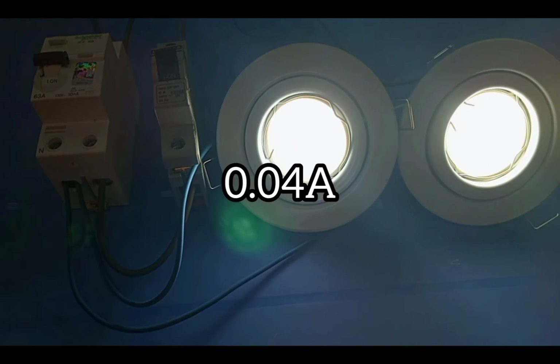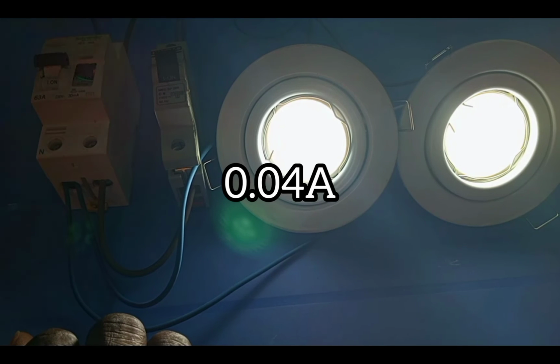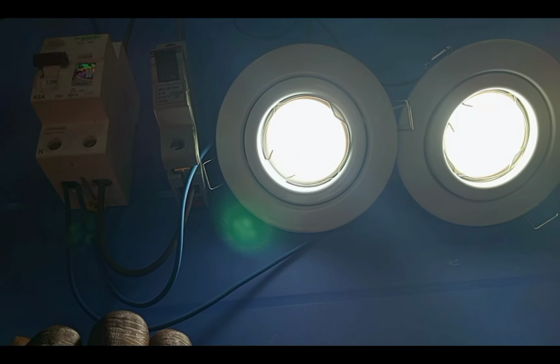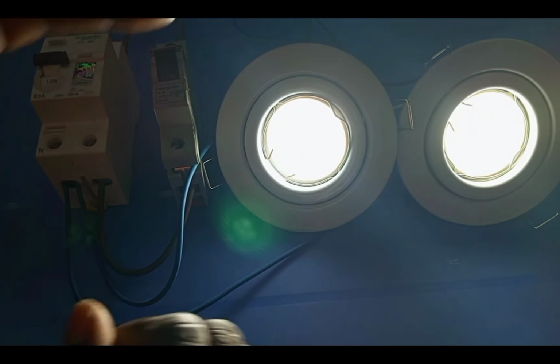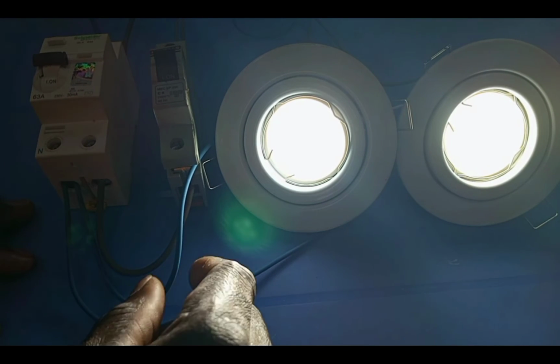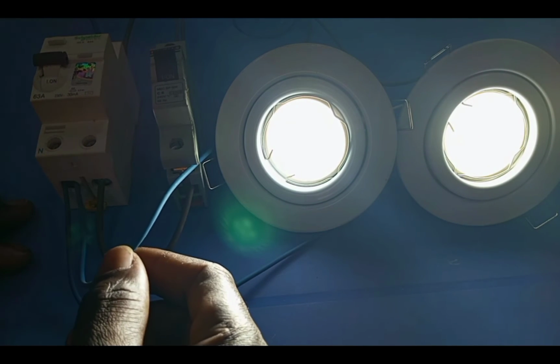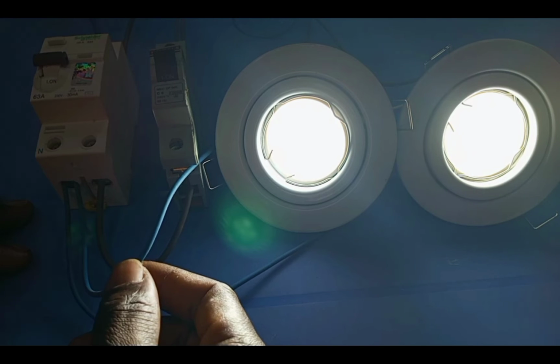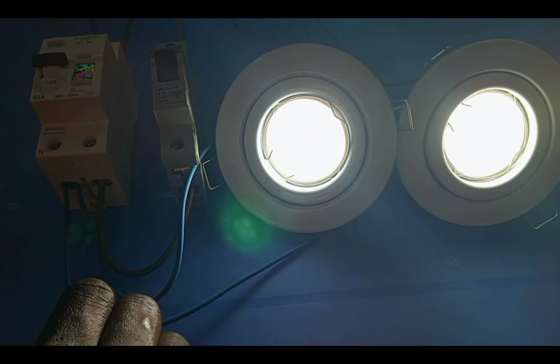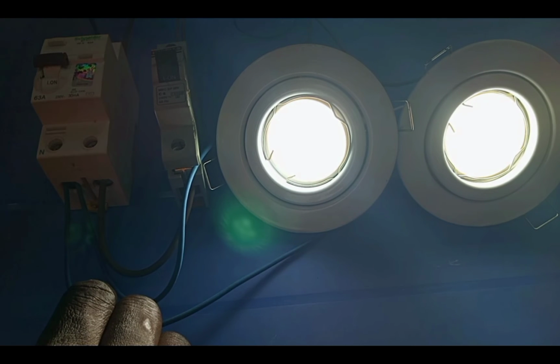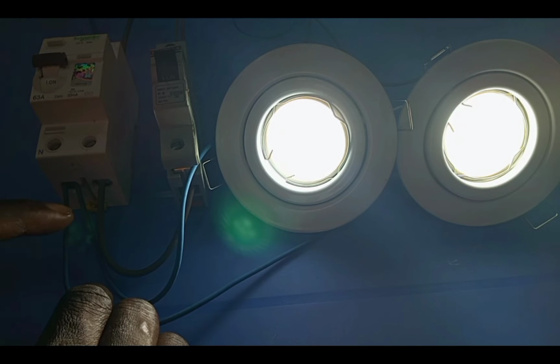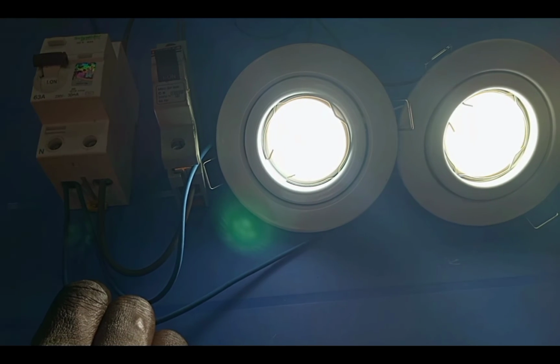All right, so in this case, 0.04 amps flows through the live wire to the lamps, but when it's coming back, it's only 0.02 amp that will be flowing. And so there will be an imbalance of 0.02 amps. It means you have 0.04 amps through the live wires, but you have only 0.02 amps going back through the neutral wire. And so the RCD will trip.